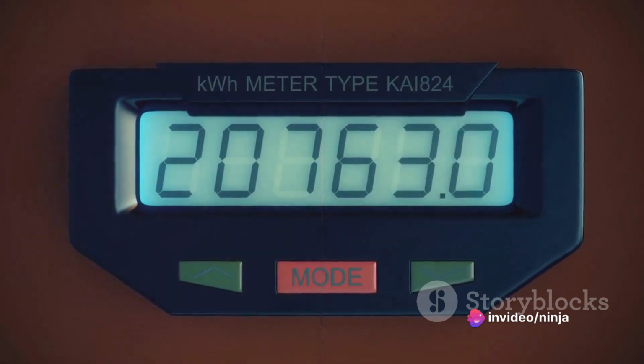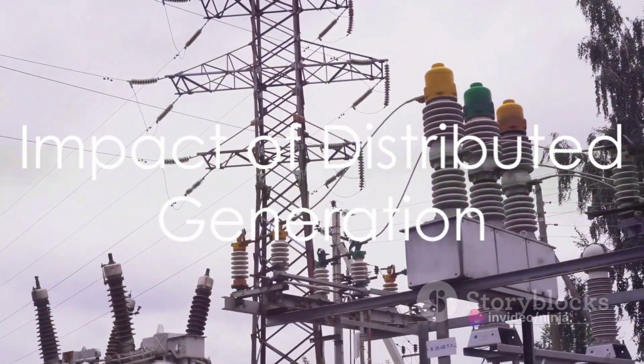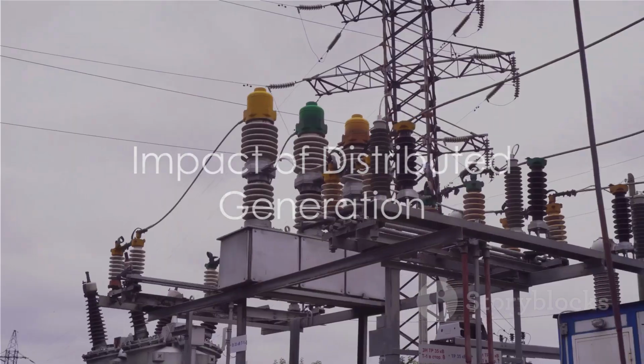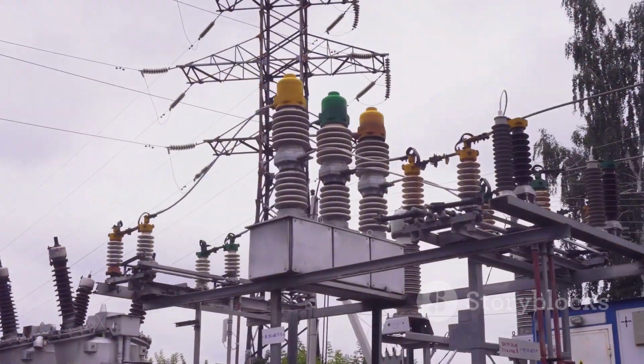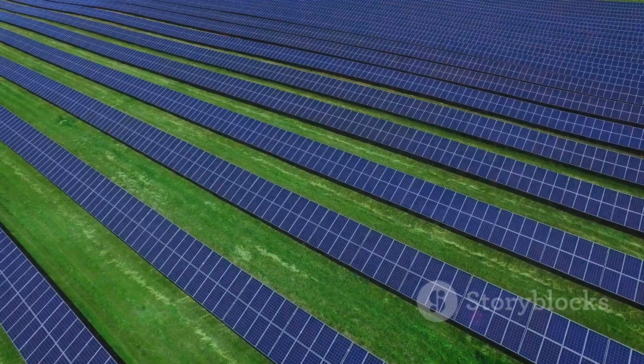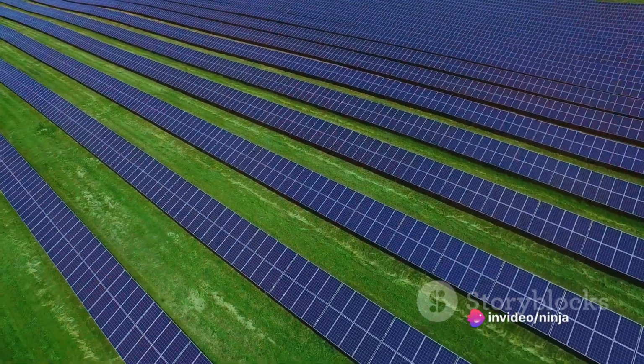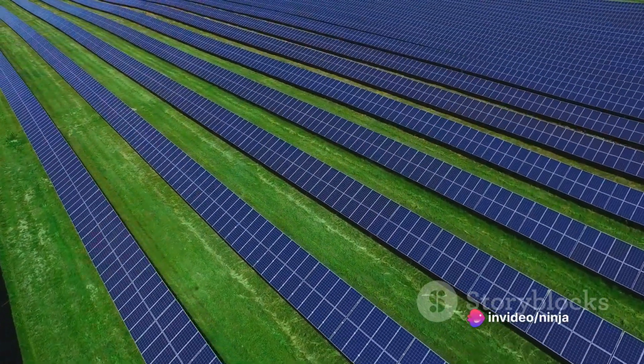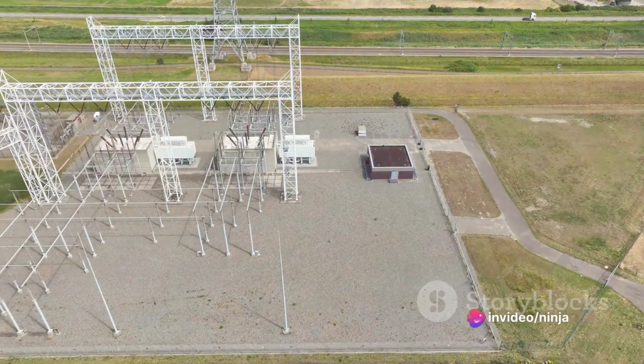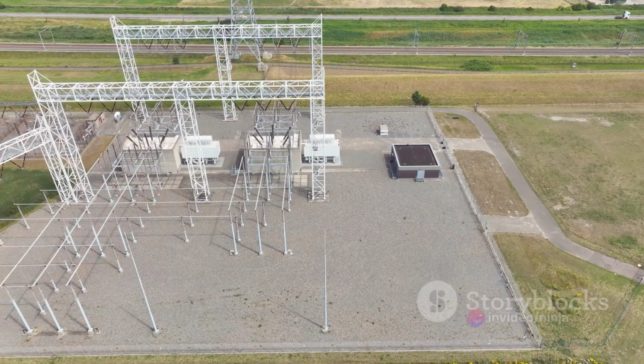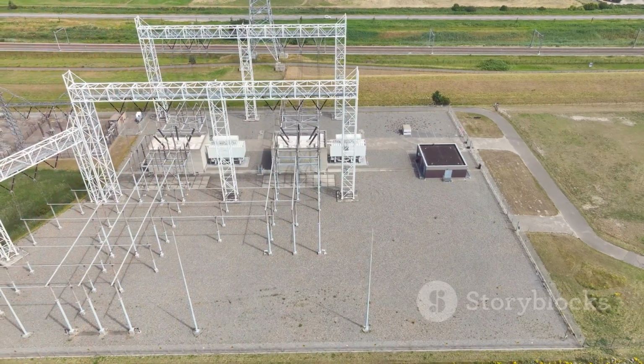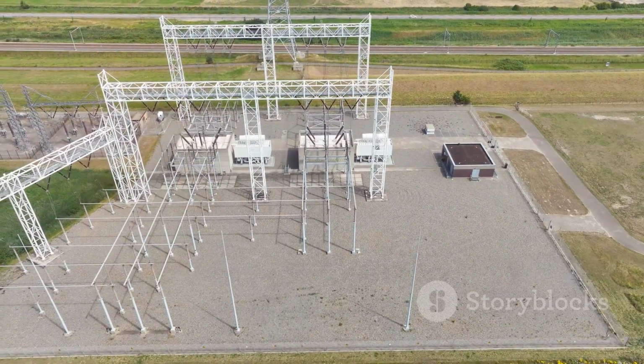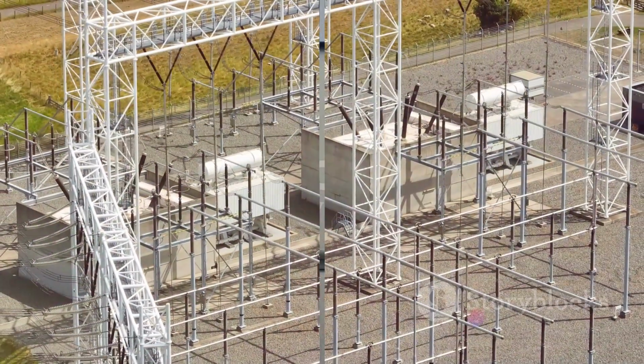The introduction of distributed generation results in less voltage drop when the generator is producing active power. This leads to a smaller overvoltage margin, and the maximum voltage may even exceed the overvoltage limit. When this happens, the power system no longer fulfills its primary aim to maintain the voltage magnitude within limits, and the hosting capacity is exceeded.